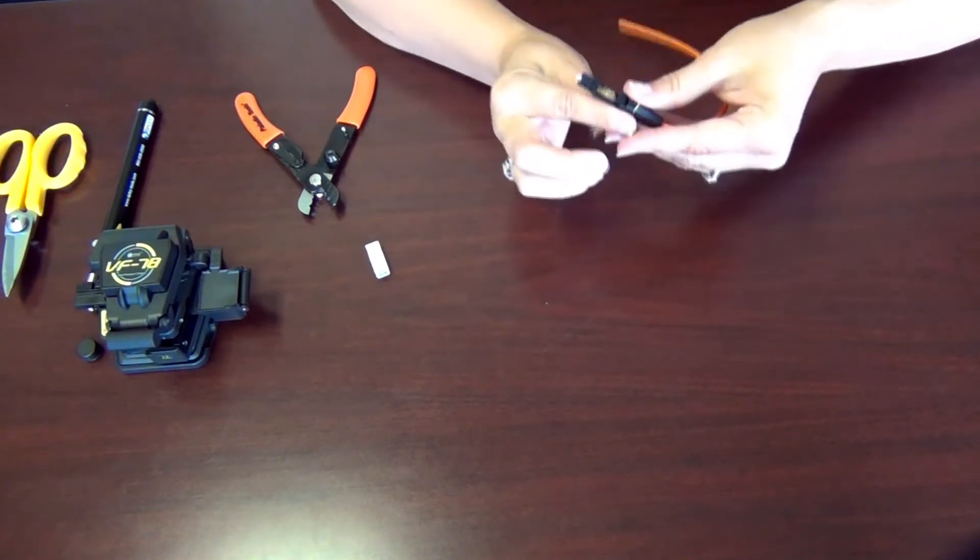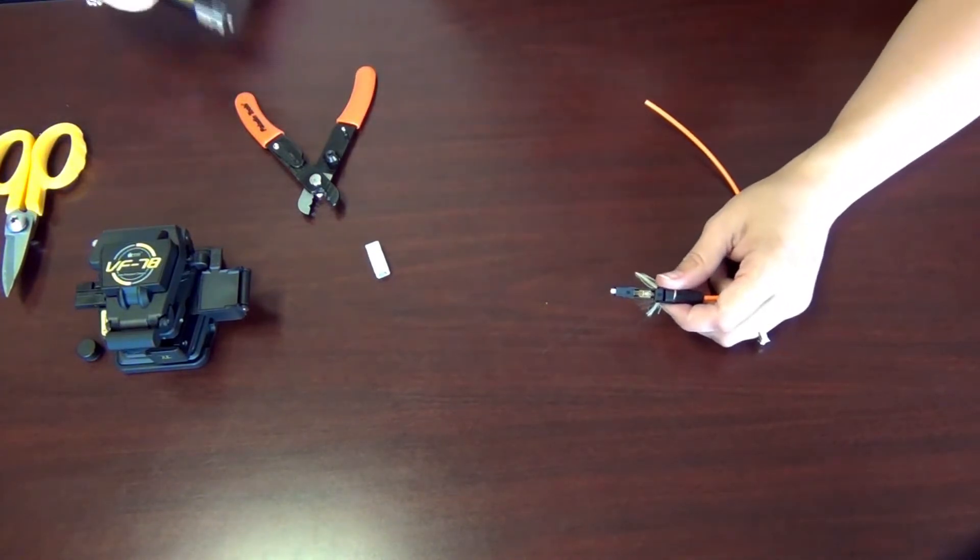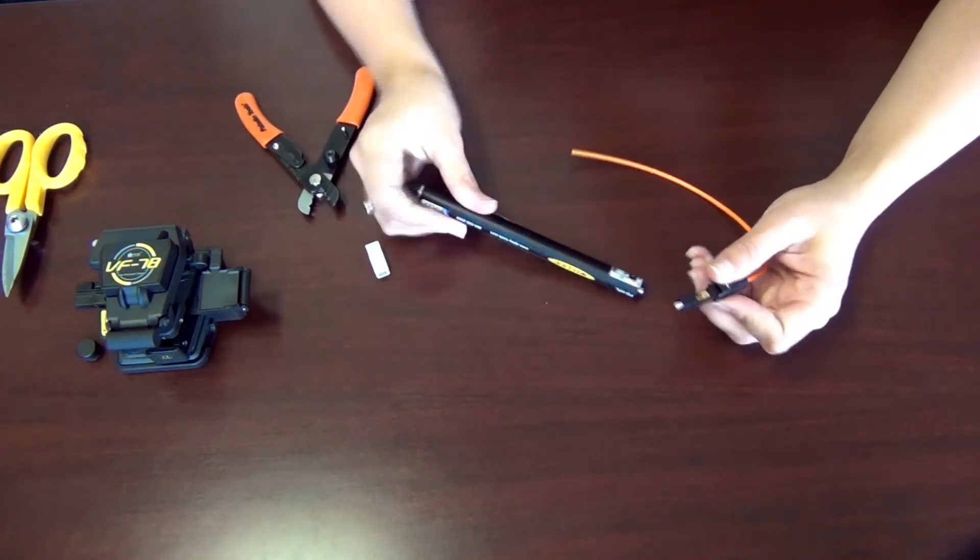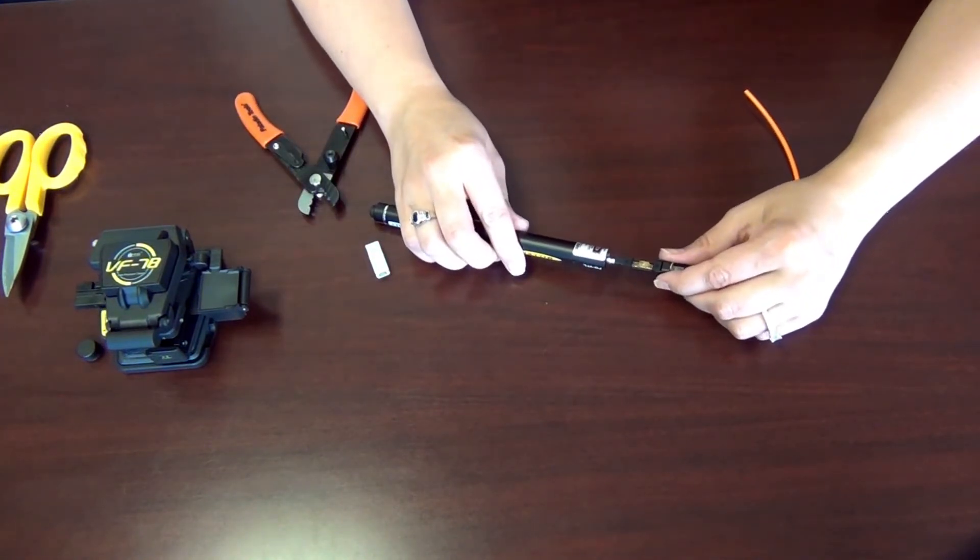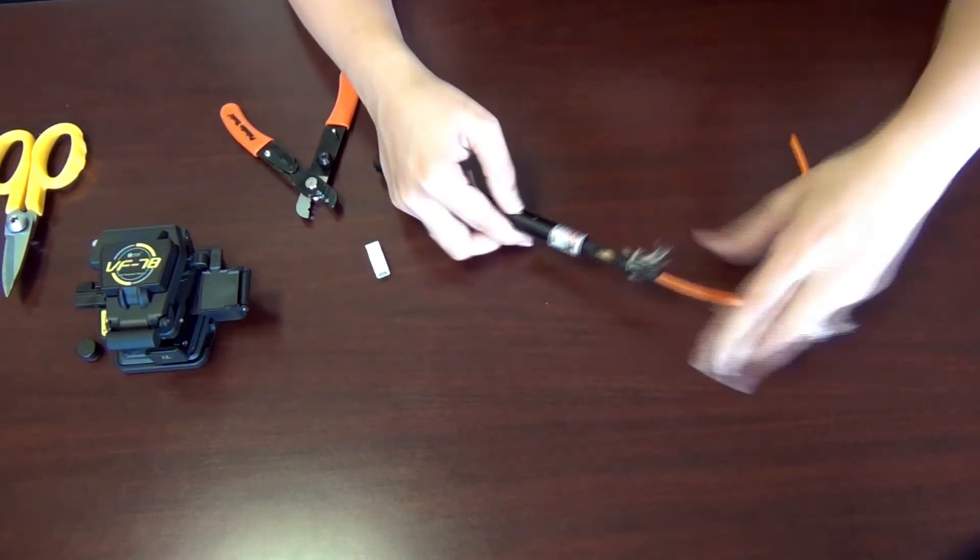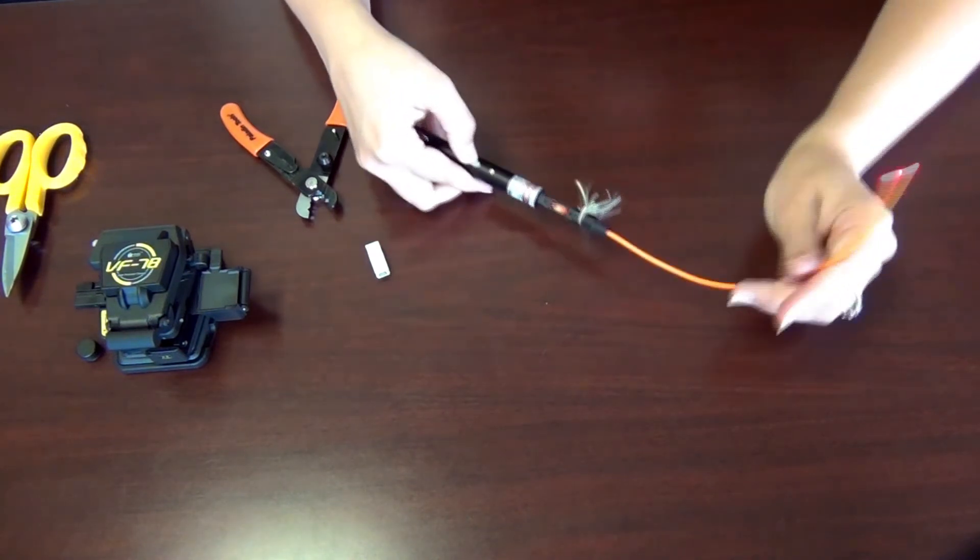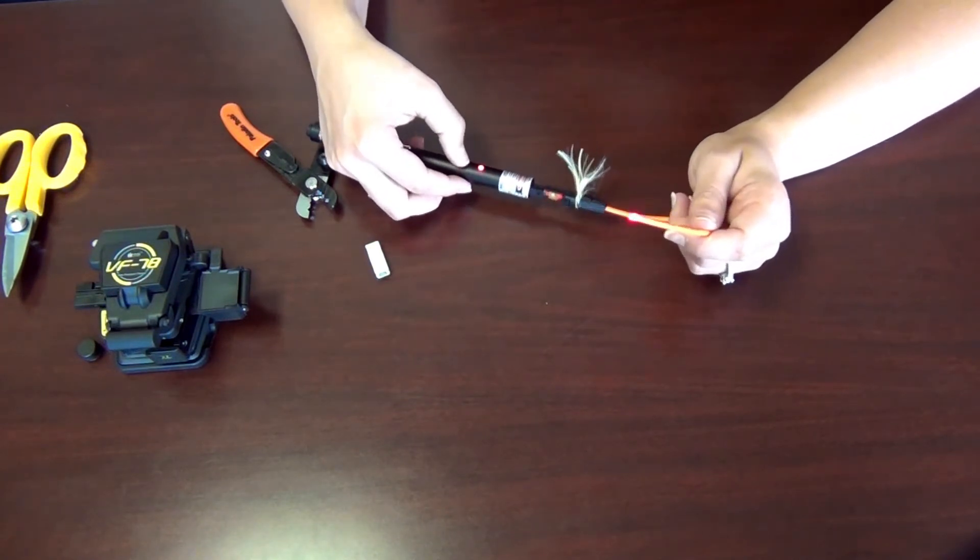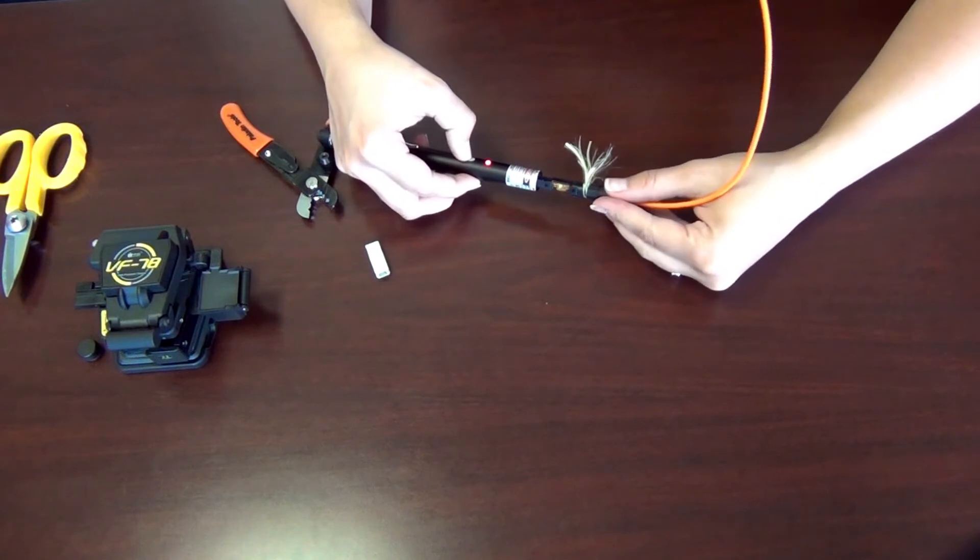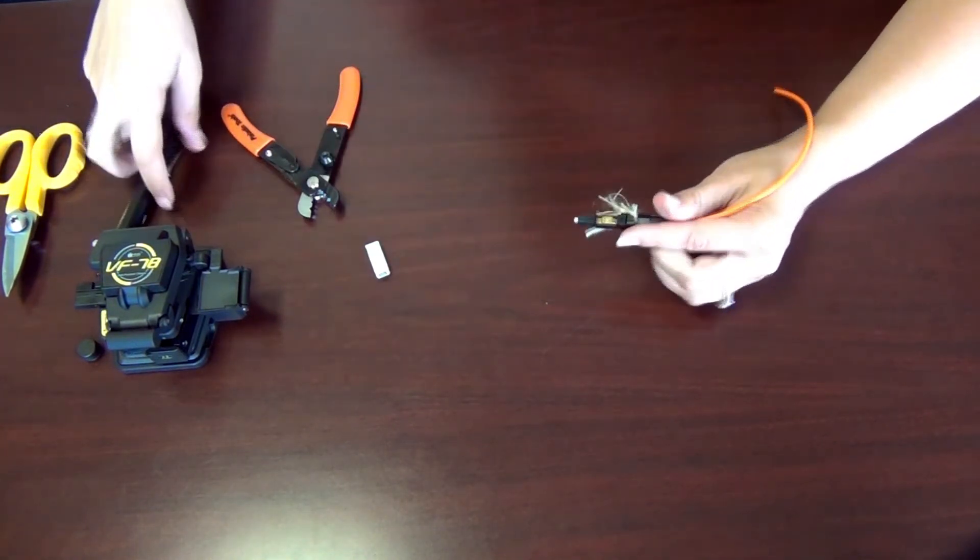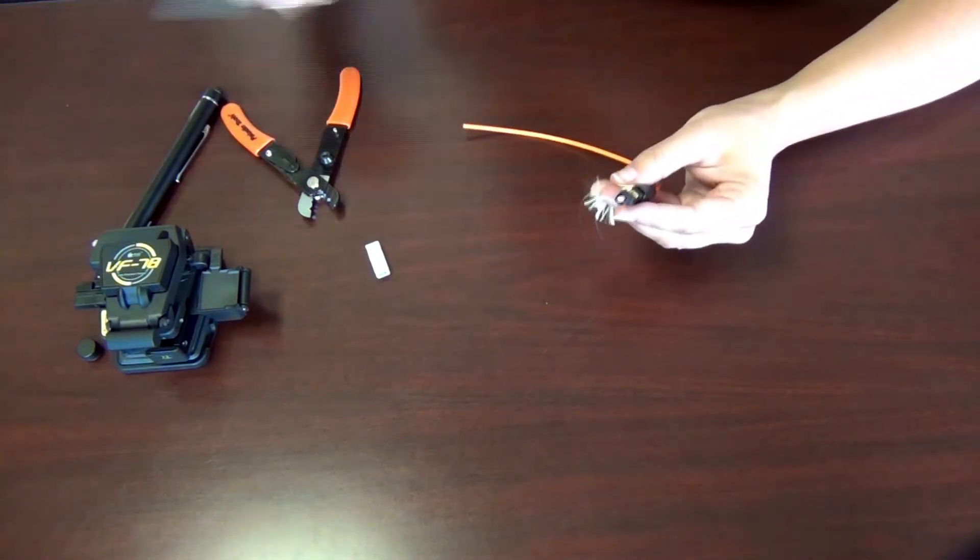Now before we finish this off we want to make sure that we test it so that it's working. Here's our tester. Turn the tester on, get the tester end onto the connector snugly. Push and press the button, and if it lights up on the other end like that, that means we've terminated it properly. Go ahead and turn that off, and then just cut these Kevlar ends so they stay out of your way.